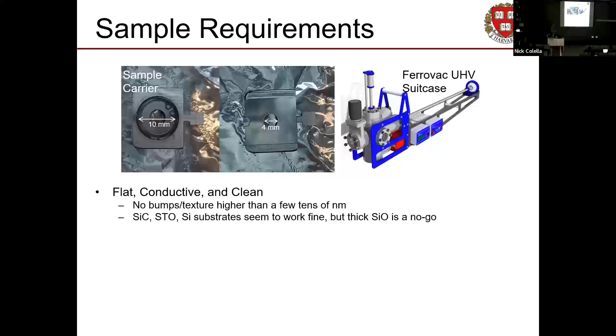It has to be clean. I already mentioned this, but your sample's got to be clean, and this is tough. Everything that comes out here into the world, everything you've ever touched, seen, unless you do this sort of work, has at least a monolayer of water on it. Even stuff that you think is completely dry has a monolayer of water on it, and surface tension is just that strong. And if you want to get that water back off, you got to heat it up real hot. And so under UHV conditions, we got to get that water off because we don't want to see it in LEEM. We got to heat up to at least 120 degrees, usually more like 300 or 400 degrees.